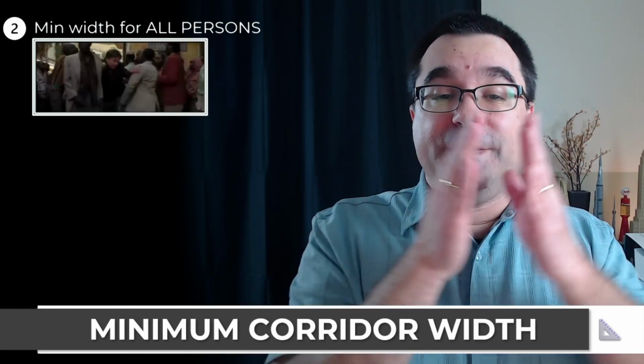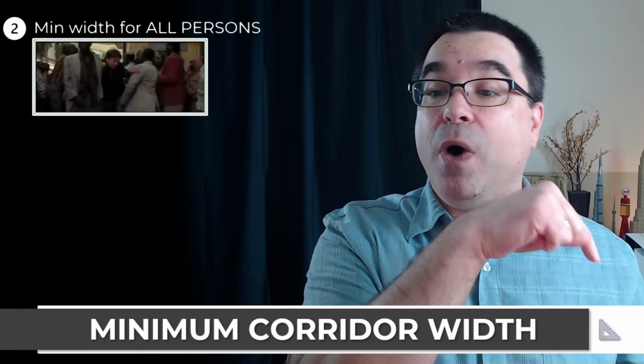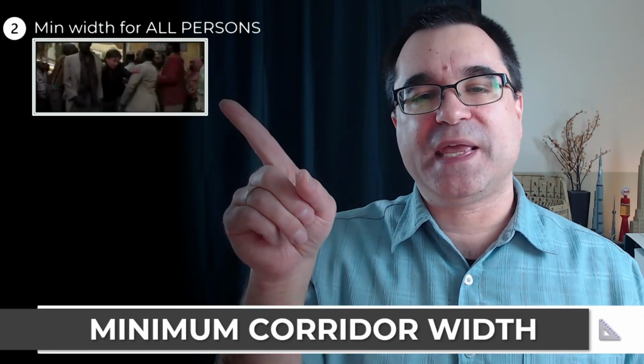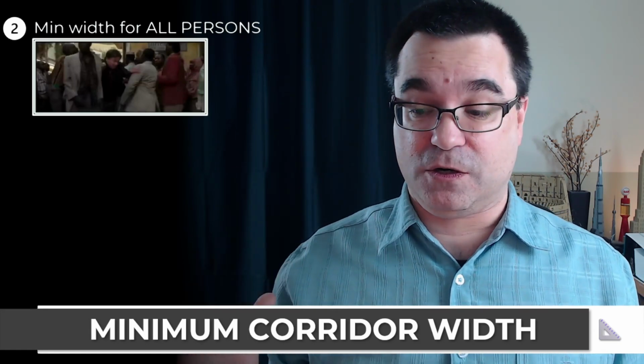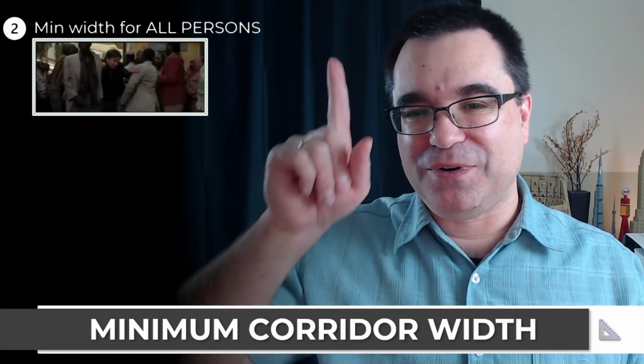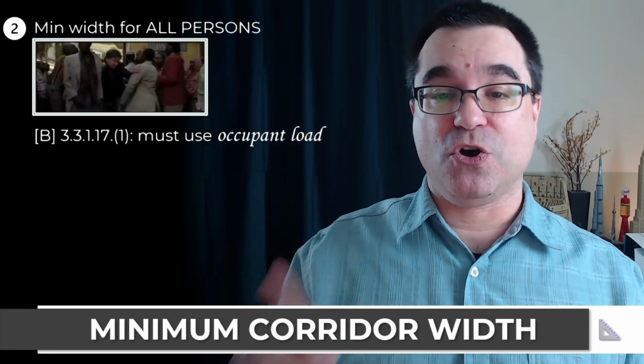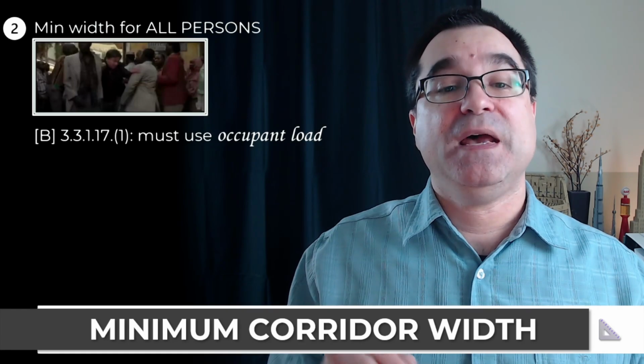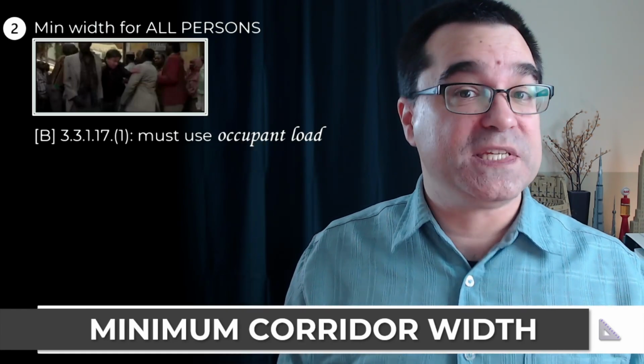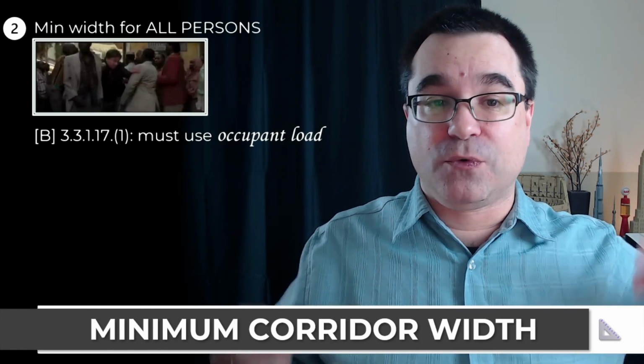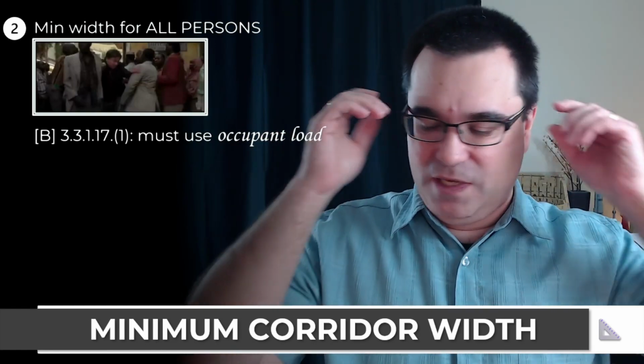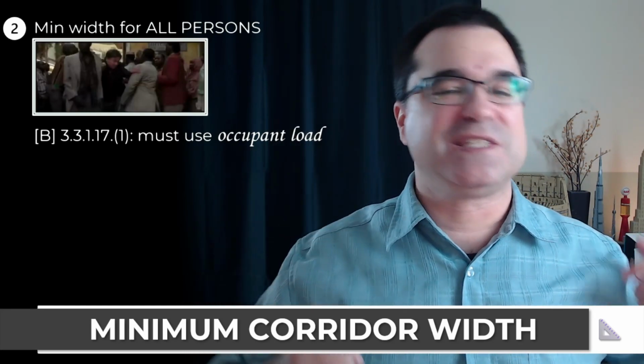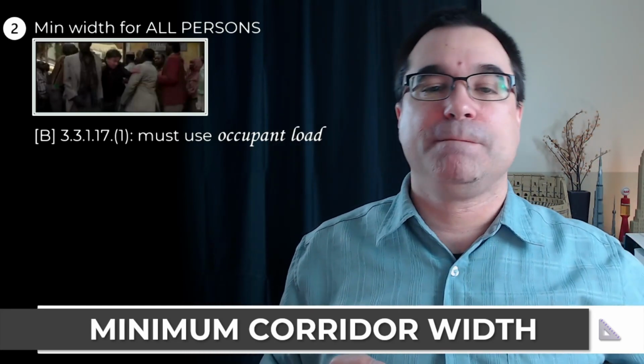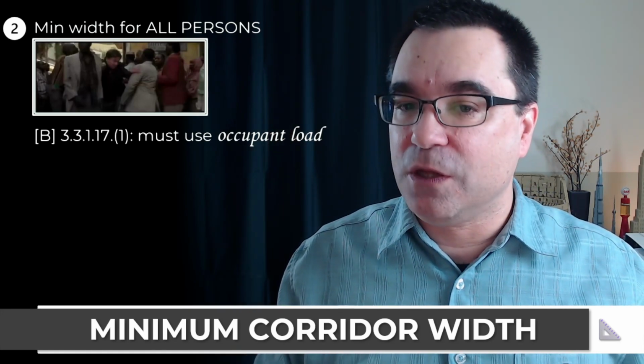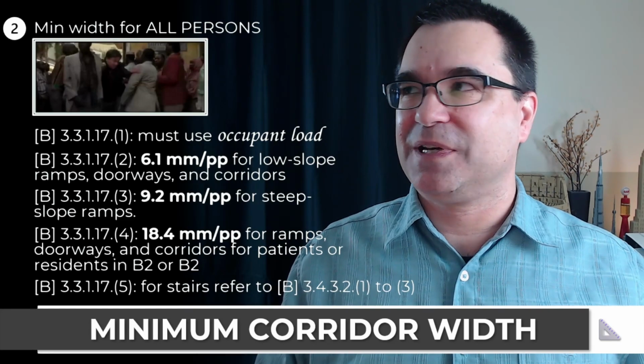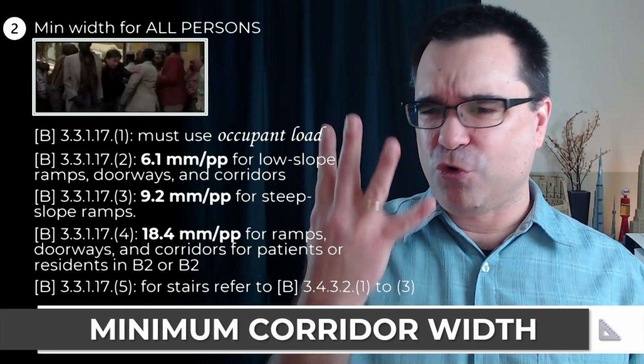Now, we figured out those were the minimum geometric dimensions for one person to get through. What about accounting for all the people that could be there? As you remember, figuring out how many people are going to be in a space is called the occupant load of that space. So in fact, sentence 3.3.1.17.1 says that to figure out the minimum width of a corridor or a door or non-exit ramps or non-exit stairs, you must also use the occupant load. We know how to do that, right? Topic 3 and 4, I think it was.